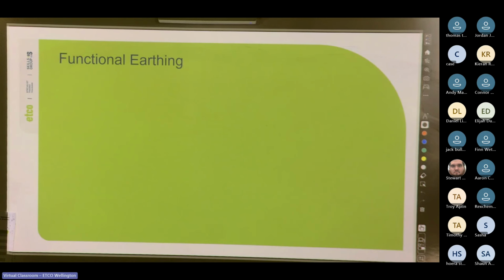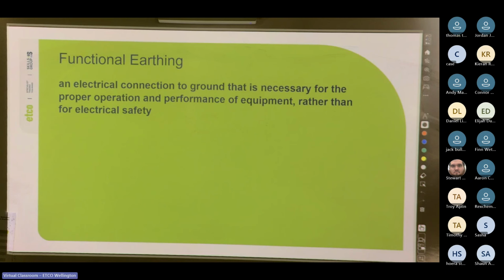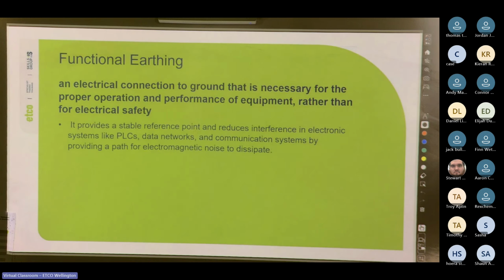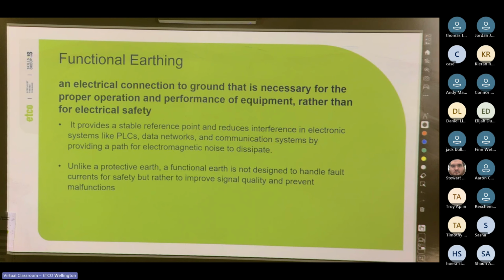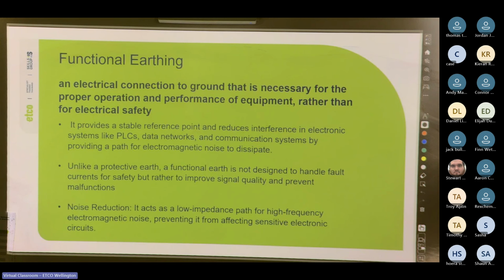And then we have functional earthing. It's an electrical connection to ground that's necessary for the proper operation of equipment rather than for electrical safety. It provides a stable reference point and reduces interference in electronic systems like PLCs and data networks. Unlike a protective earthing conductor, it's not designed to handle fault current for safety, but rather to improve signal quality and prevent malfunctions. They're used for noise reduction, so it acts as a low impedance path for high frequency magnetic noise, preventing it from affecting sensitive electronic circuits.